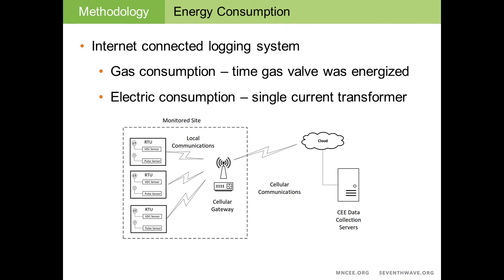The single CT transformer, or single transformer method, has been used successfully in a number of other research projects, and we did extensive research on how to implement that measurement. To get away from that standard logging, we just selected an internet-based logger that was able to establish local communications between the rooftop units and a cellular gateway, and then use cellular communication to go back to CE's data collection servers in order to collect the data in near real time.